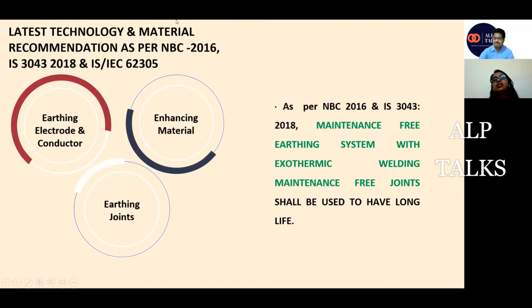Exactly. Secondly, this copper coating has been molecularly bonded over the steel, so no one can separate copper from steel. So it has zero scrap value. If someone thought that it is copper and he will steal it, it will be of zero value for him or her, because both have different melting temperatures, so separating them would require two furnaces of different temperatures. So this is the advantage of this material, that it is theft-free and cost-effective. Theft is a major issue in India, where pure copper is usually stolen from the sites. This happens many times. So it is also not an issue with copper bonded rods. Good. Yeah, proceed here.